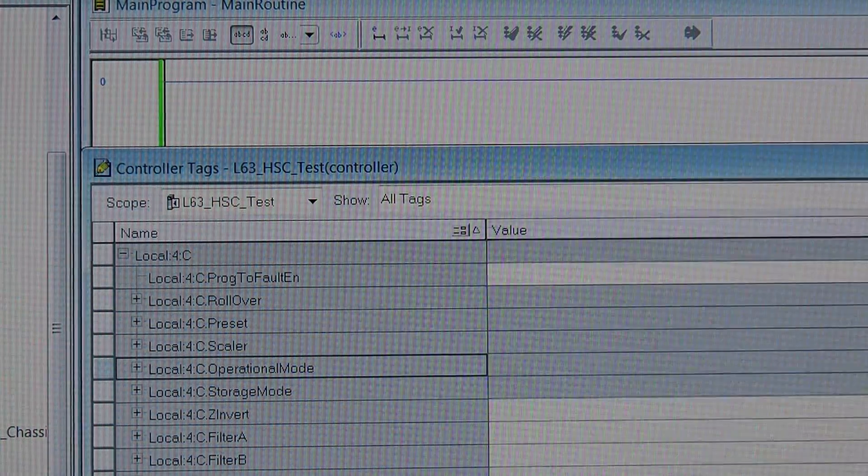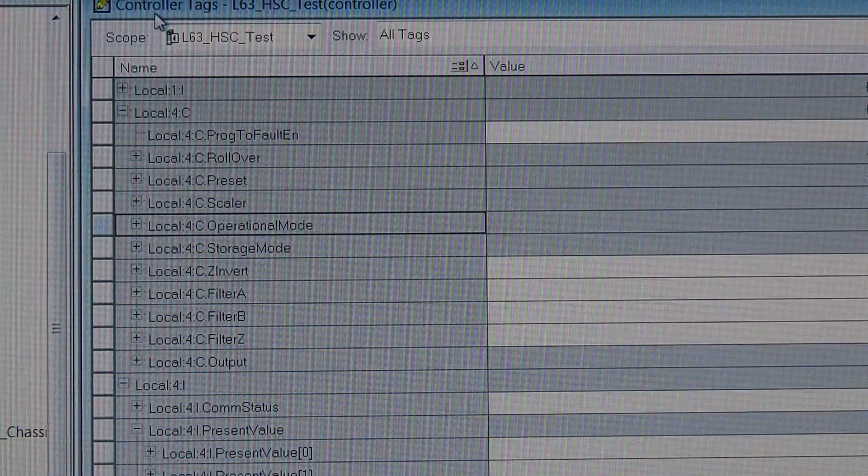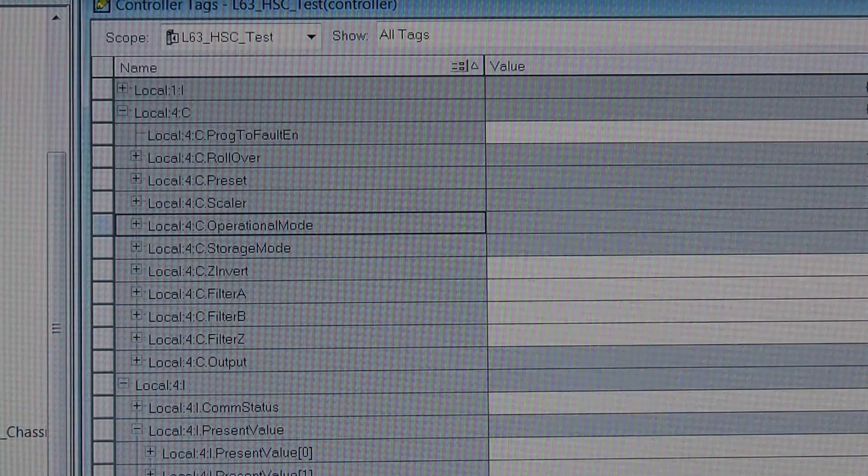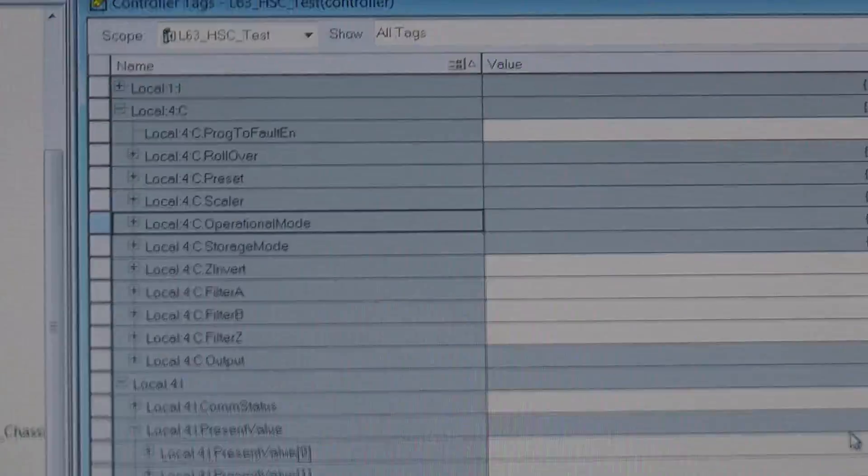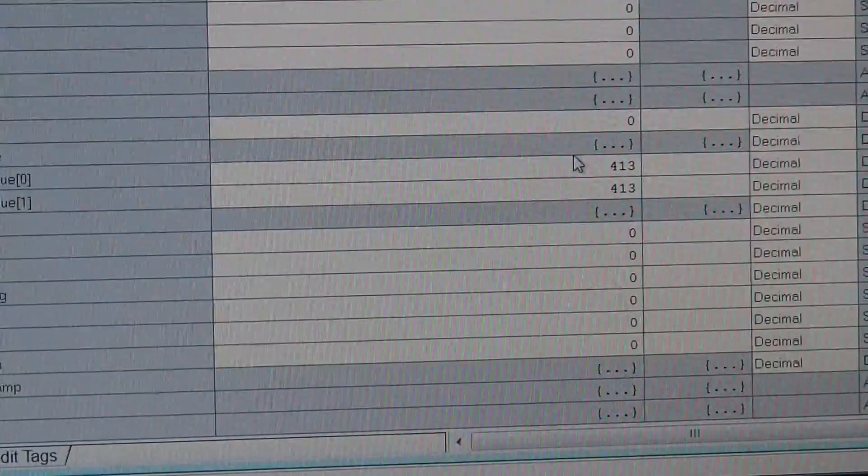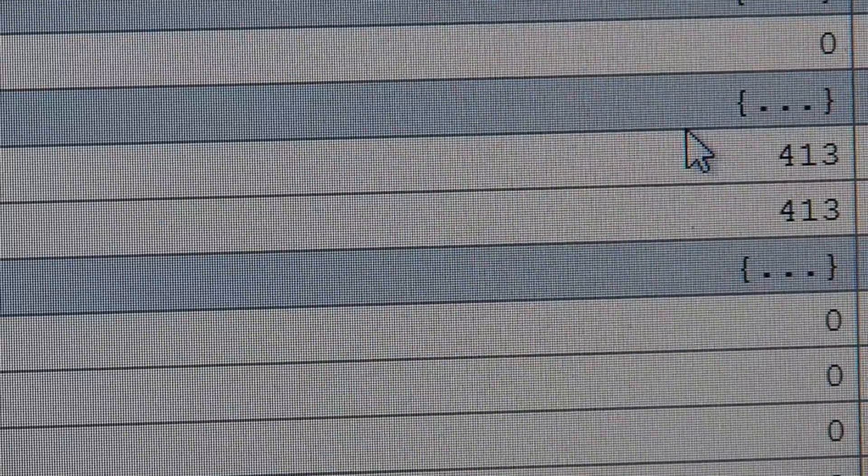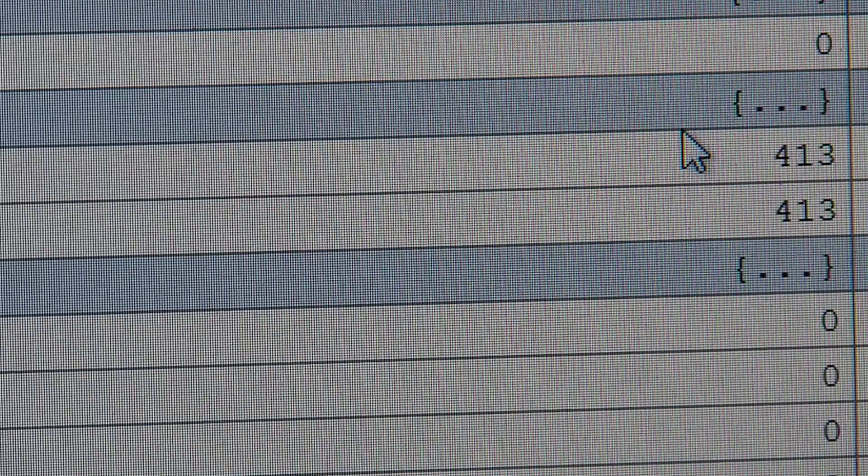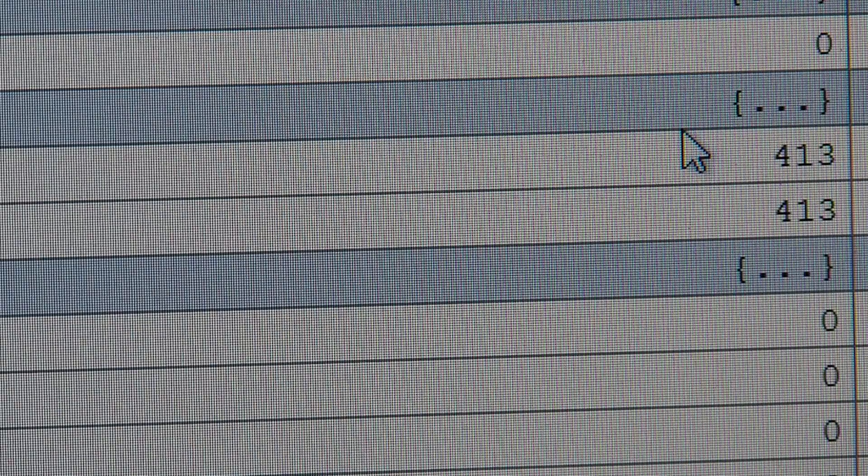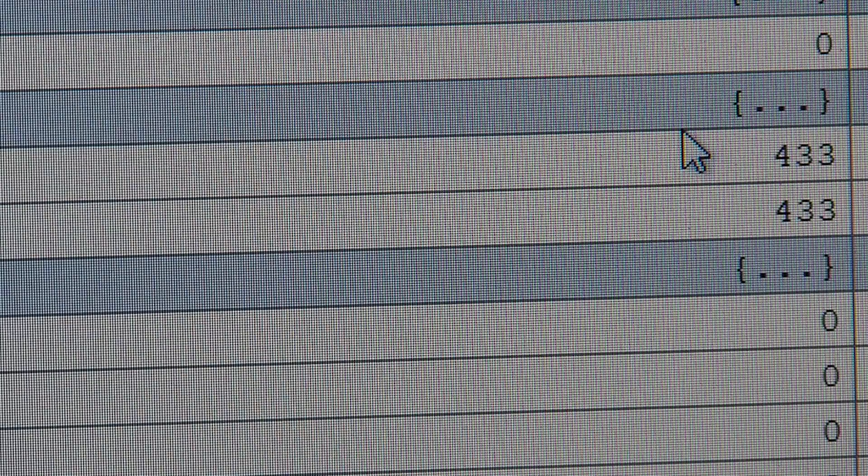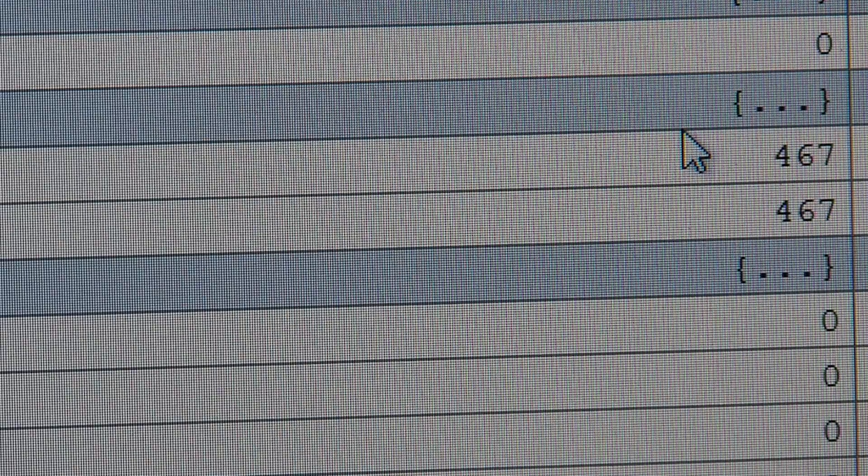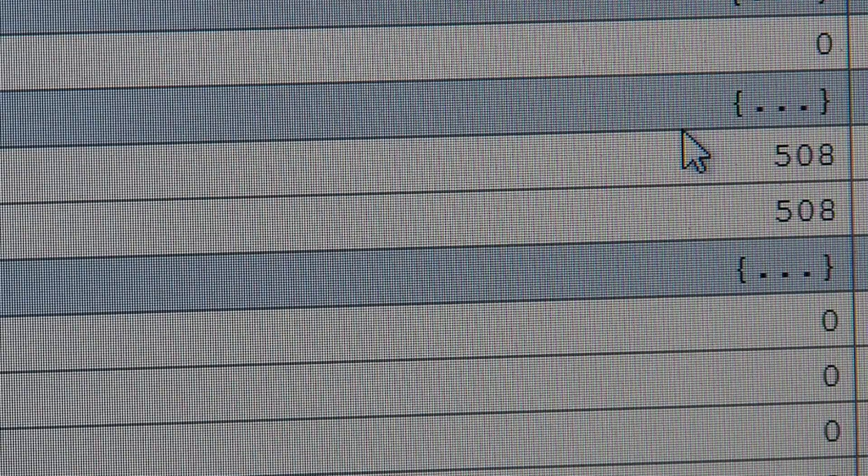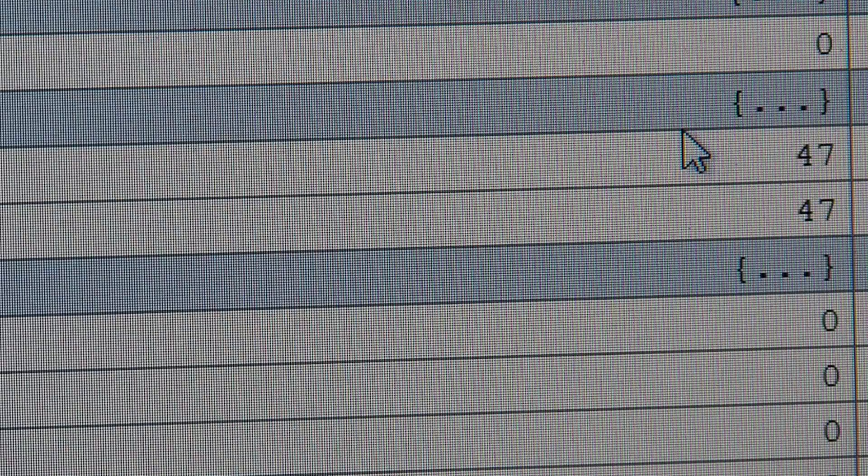Now, in this screen, we have the controller tags, and if you look right down, we zoom right in. So, there's our current encoder count, and if I turn my encoder shaft, you can see how it goes up and up and up. It's, being a 250 pulse, it takes two full revolutions, 510, and rolled over to 10, reset. Same thing, just keep going, and it'll do this forever.